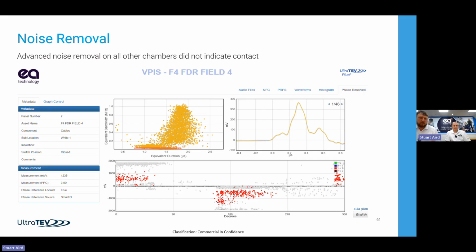So going back to that question in the survey, would you take an outage? This allows us to go from, okay, there's something going on on that panel, to having confidence that it does look like PD, not some other external noise. So that story is getting stronger and stronger all the time, even from handheld equipment. These sorts of techniques have existed on some permanent monitoring systems, high-end ones, for a while, but we've built one of the world's first to get this into handheld instruments, and we're about to bring this feature to you for our services.